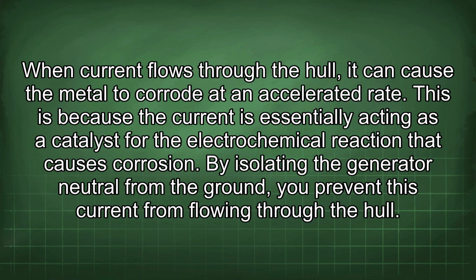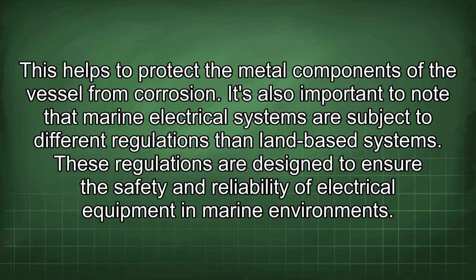When current flows through the hull, it can cause the metal to corrode at an accelerated rate. This is because the current is essentially acting as a catalyst for the electrochemical reaction that causes corrosion. By isolating the generator neutral from the ground, you prevent this current from flowing through the hull. This helps to protect the metal components of the vessel from corrosion.